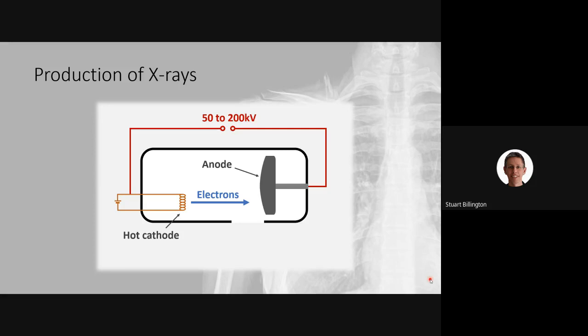When the electron collides with the tungsten anode, it basically produces a shower of X-rays, and those X-rays will be emitted in all directions, but the casing is shielded, and there is just a small window in the bottom of it. And if you've ever had an X-ray machine hover over the top of you, you'll have seen the window. There's usually a light bulb inside it, which shines visible light through the window so that the person operating the machine can see where the X-rays are going to land by looking at where the visible light lands.